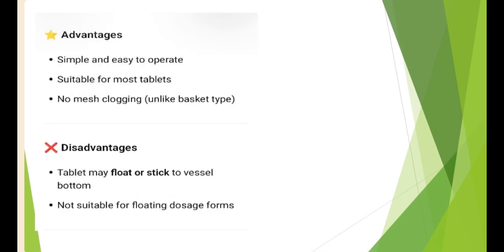Advantages of paddle type dissolution apparatus. It is easy and simple to operate, suitable for most tablets, and has no mesh clogging, unlike the basket type.